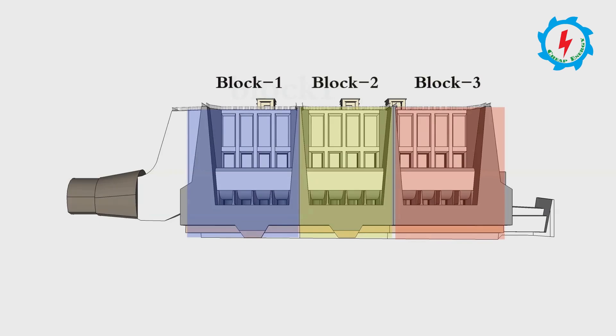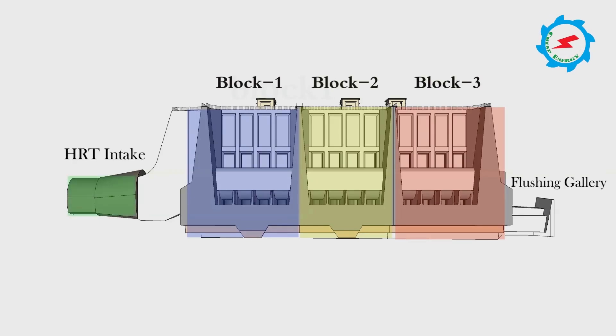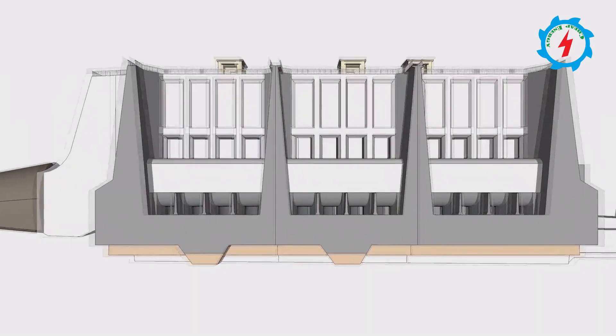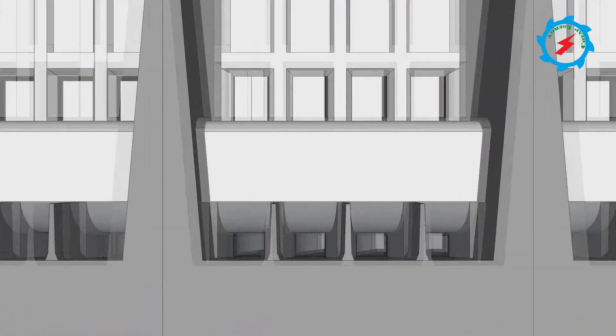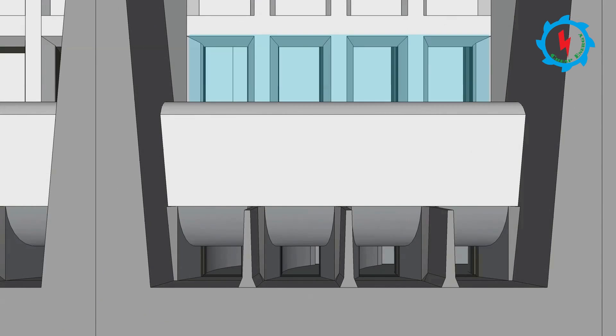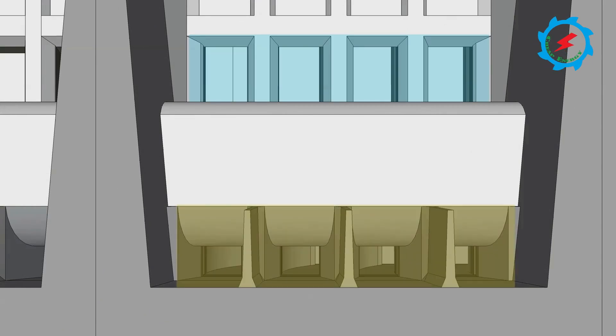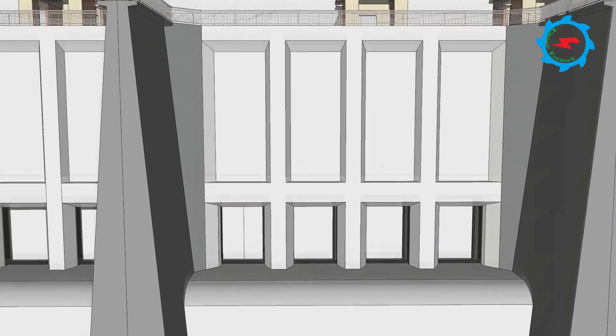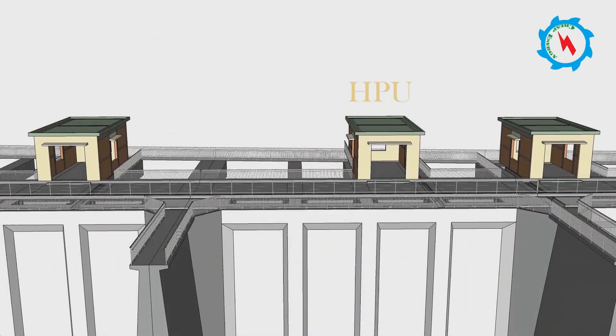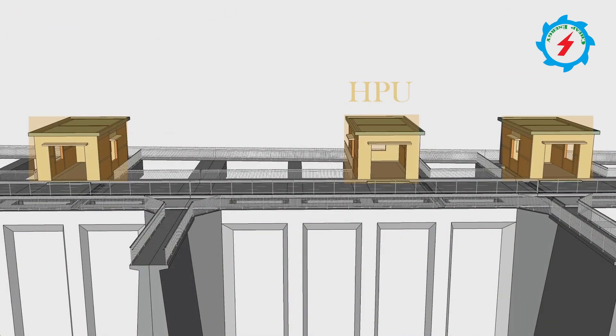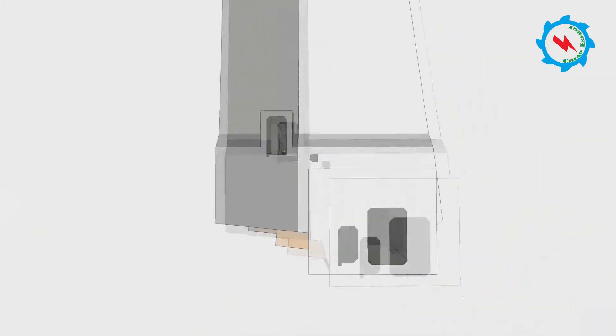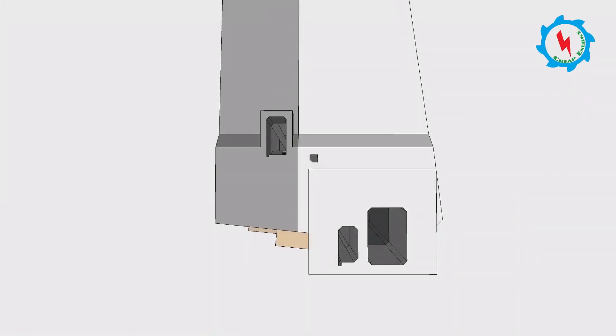Headrace connection with collecting canal and flushing gallery. Upper-level outlet gates, four in each block, were provided for passing water into collecting canal, and four undersluice flushing gates at lower levels. The collecting canal gates has been designed to operate locally from HPU control units placed inside of the three respective concrete buildings on outlet block deck.